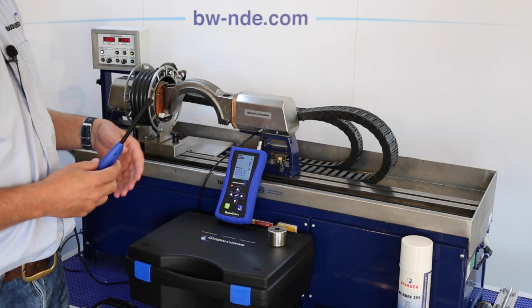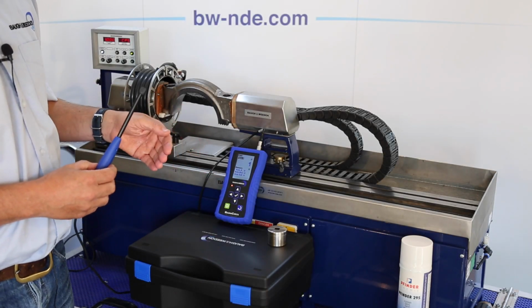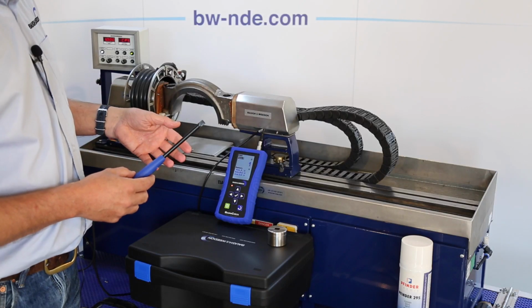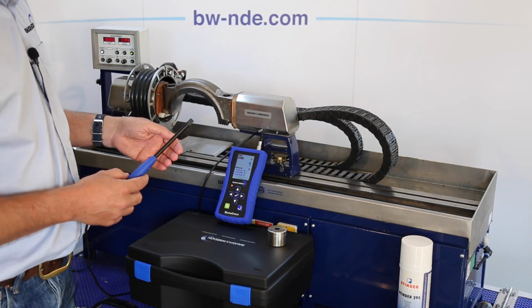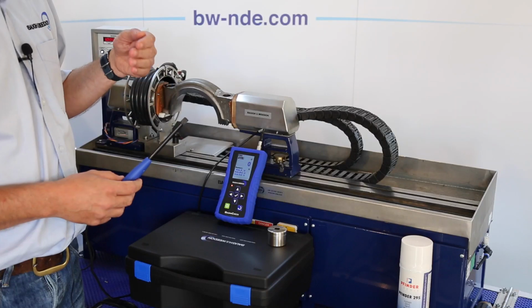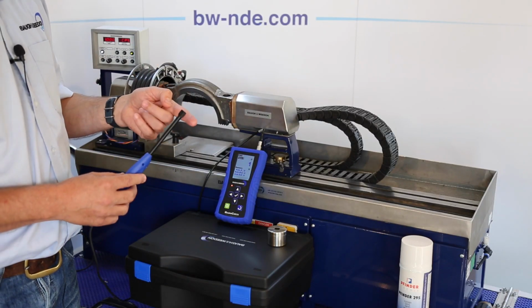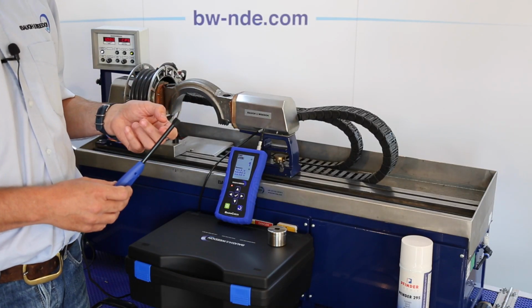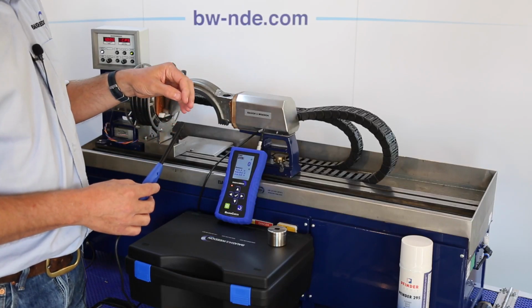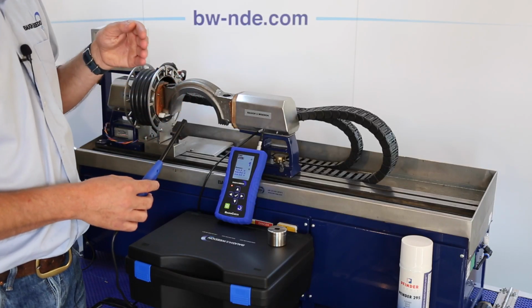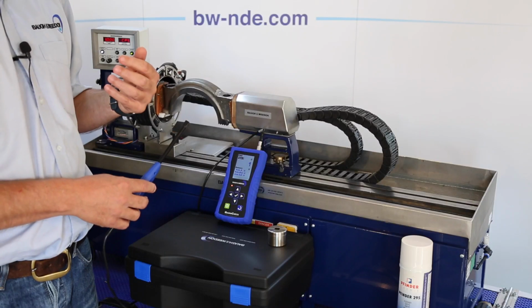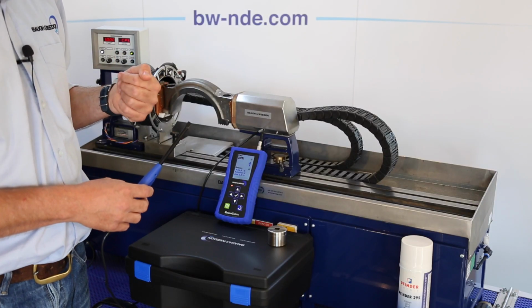Okay, you've already seen the meter used in free field mode. To use the gauge to its full potential, we also have an option of selecting an individual face to put onto the surface of the part. It's called face select mode. What it does is reject any magnetic fields that we don't want to see that aren't going to be beneficial to our MPI test.